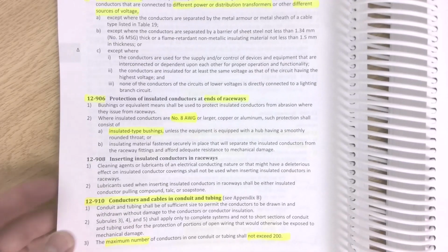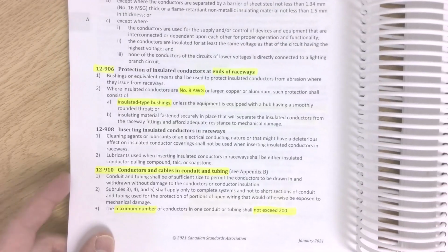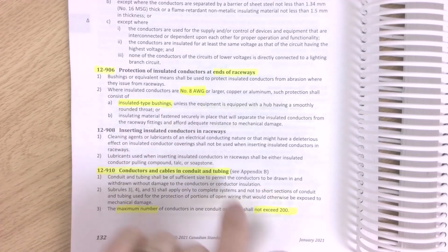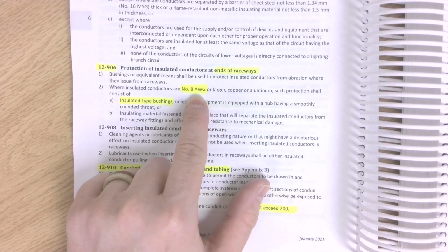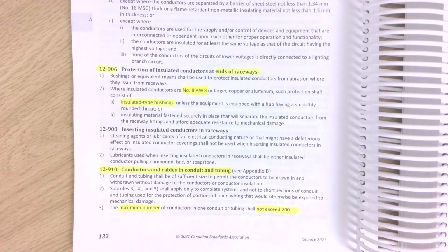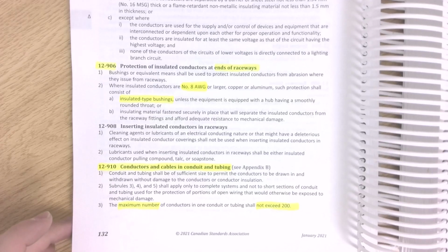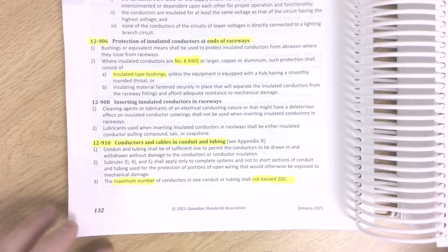And moving on and just looking at a couple of the specific rules in 12-900. 12-906 is telling us that we have to basically have a bushing or something that will protect a conductor that's 8 gauge or larger. You could also look at, you don't need the bushing for anything smaller than a number 8 gauge. That's sometimes the 2 ways I like to read things in the code book to help my brain process this wealth of data and information.